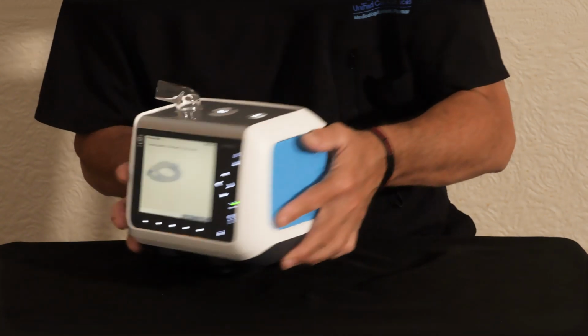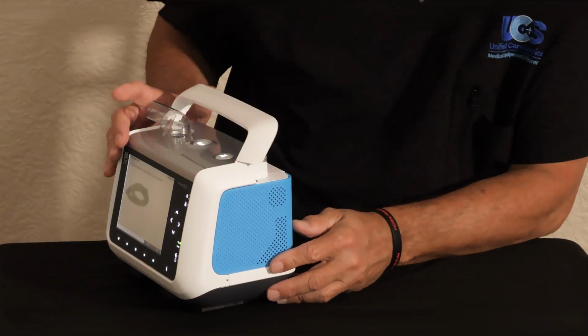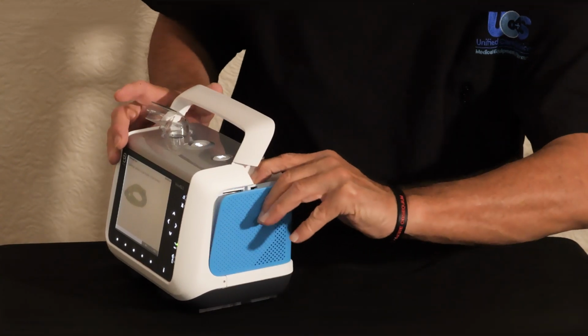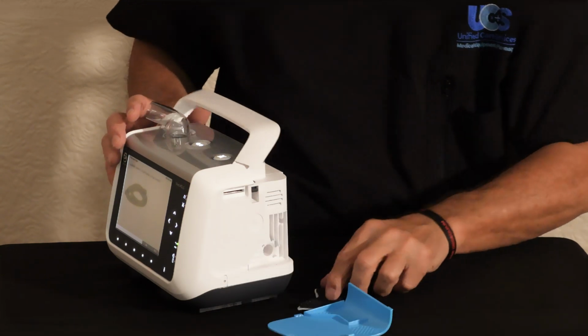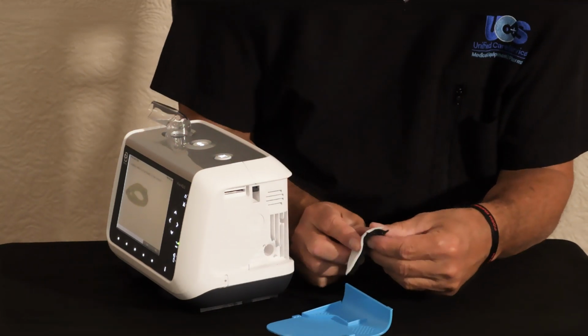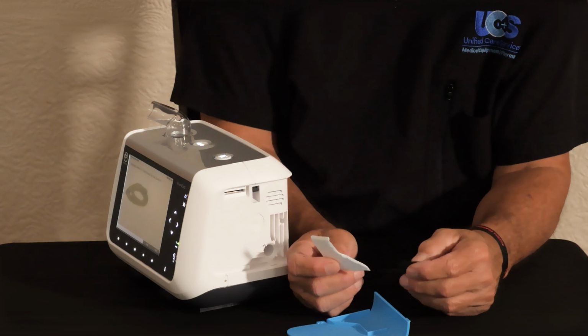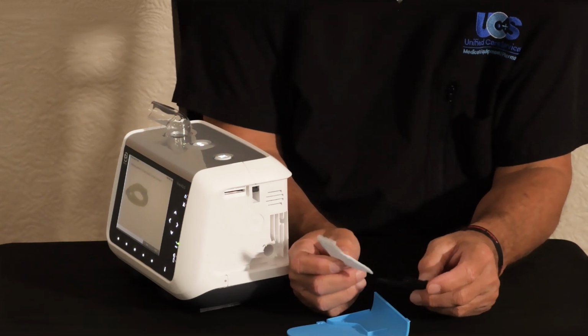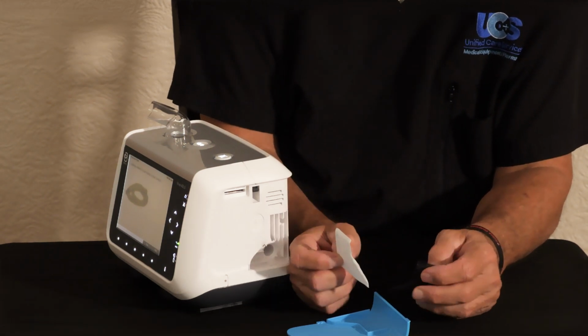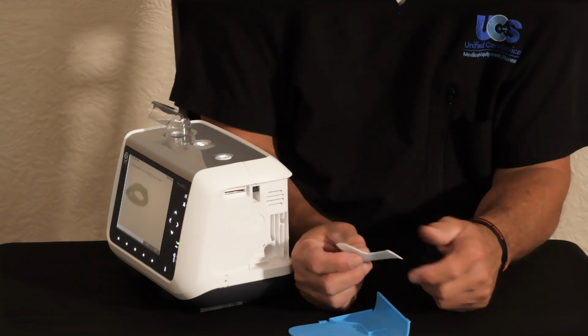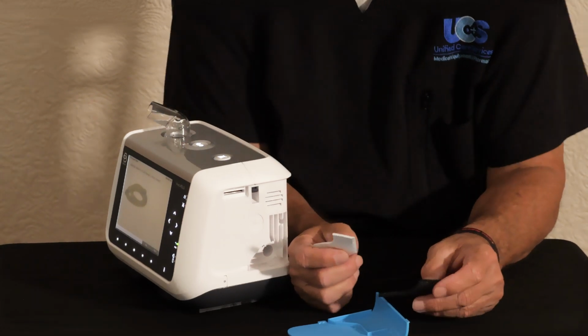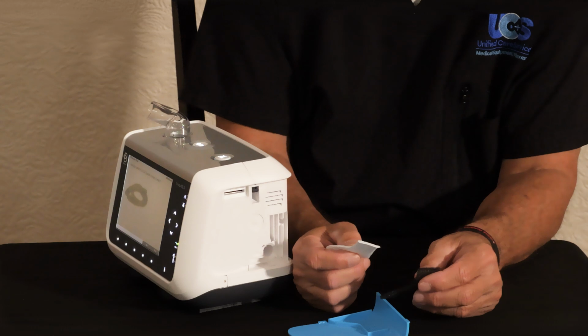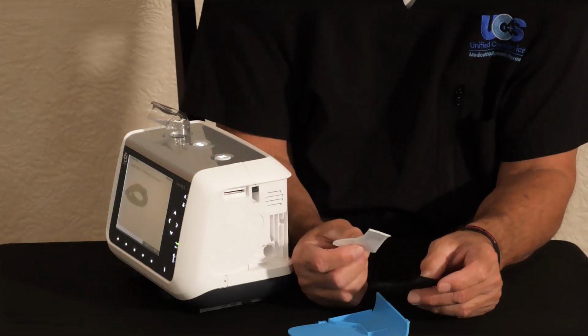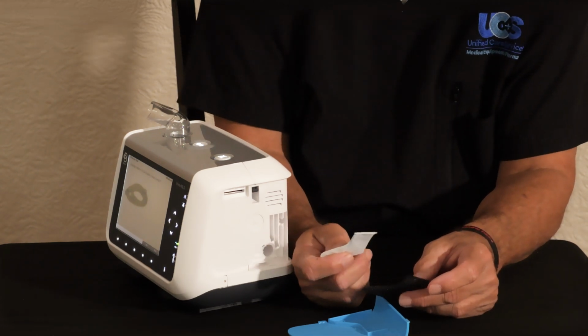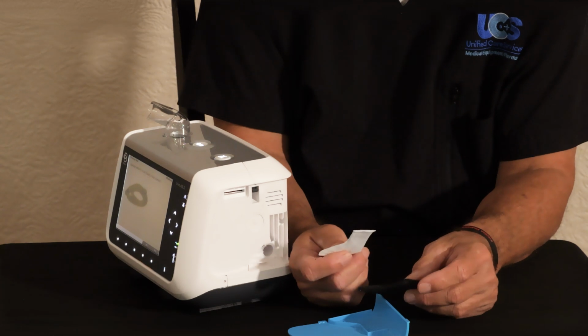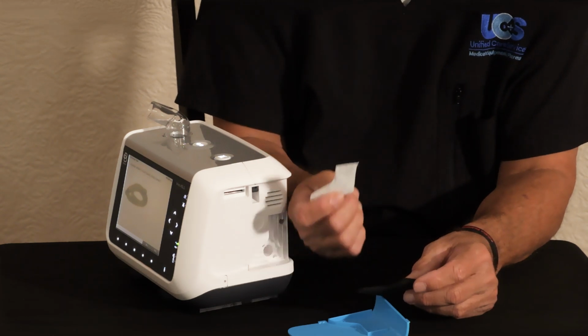On the other side of this ventilator, you have another door, and you have 2 filters here. You have a white disposable filter. This filter, you should change it on average at least once a month. If the environment is particularly dusty, you might want to consider changing this filter every 2 weeks. So if you're first starting to use it in your home, check it in 2 weeks and see if it's dirty. If it is, then replace it. If not, replace it once a month. So replace this filter, do not wash it.